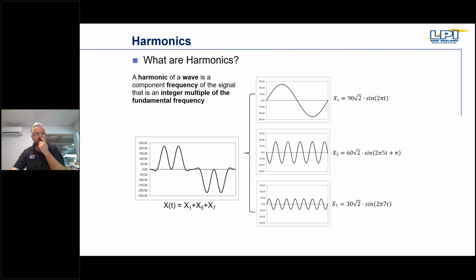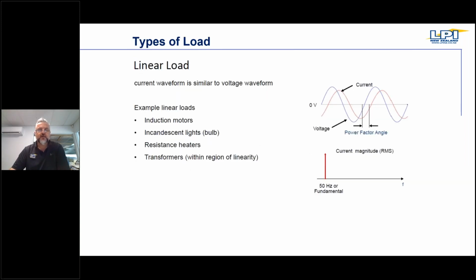Again, just for those of you that are not aware of harmonics, I understand there are a number of facility managers present at this presentation who are not electrical engineers, but basically harmonics are just multiples of the fundamental frequency. Most of you would know that our standard power is rated at 50 Hertz, so the third harmonic would be 150 Hertz, or the fifth harmonic would be 250 Hertz. And those harmonics introduce what we mentioned earlier, possible overheating of the cables that can cause a potential fire hazard, and they can also cause nuisance tripping of the breakers, and some other problems, but we won't go into those details. We can leave that for another presentation. The idea is just to give you an idea of whatever is connected with EV chargers and harmonics.